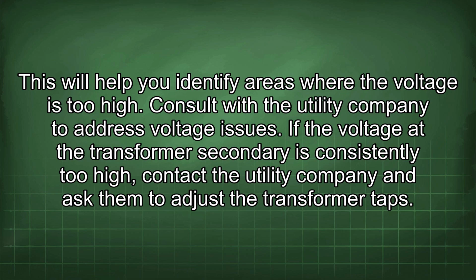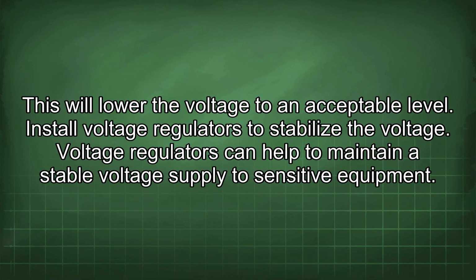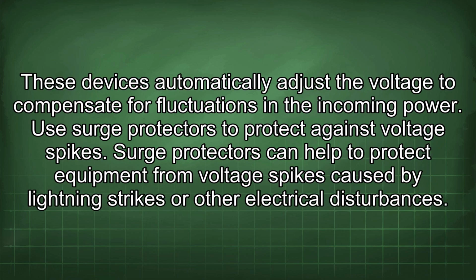Consult with the utility company to address voltage issues. If the voltage at the transformer secondary is consistently too high, contact the utility company and ask them to adjust the transformer taps. This will lower the voltage to an acceptable level. Install voltage regulators to stabilize the voltage. Voltage regulators can help to maintain a stable voltage supply to sensitive equipment. These devices automatically adjust the voltage to compensate for fluctuations in the incoming power.